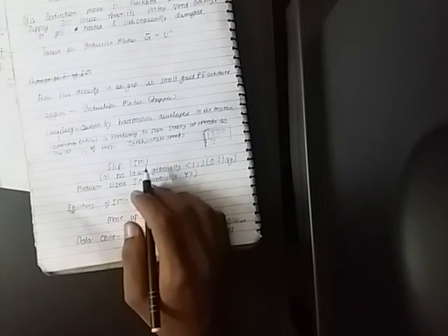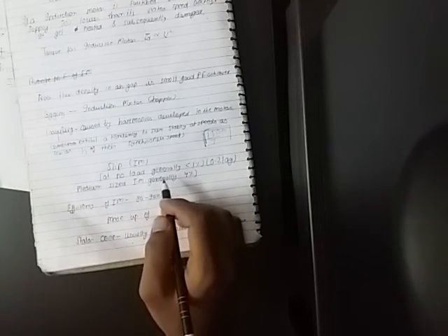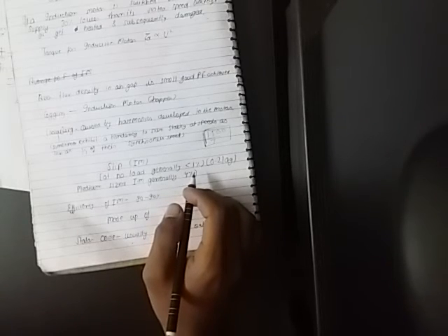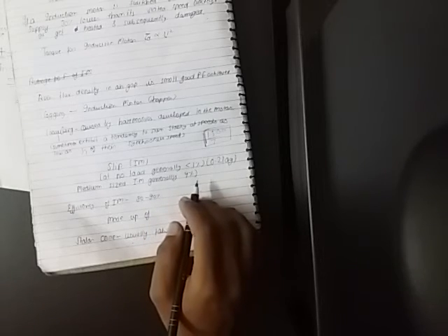At no load in the slip ring induction motor, slip is generally less than 1%. In a medium size induction motor, it is generally 4%. The stator core of an induction motor is made of silicon steel. The frame is made of cast iron. The shaft is made of carbon steel. The slip ring is made of phosphor bronze. Can an induction motor run at synchronous speed? Yes, an induction motor can run at synchronous speed, but when EMF is injected in the rotor circuit.